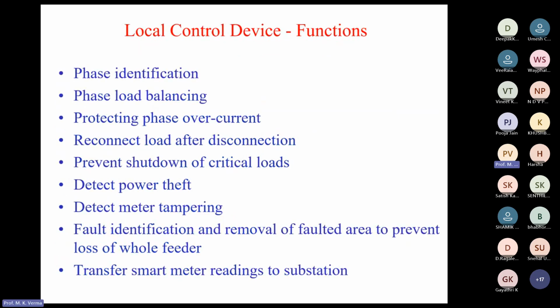The local control device's functions: it may identify the different phases and also the faulty phases, where the fault is, and it can deal with phase load balancing. It can protect the phases from overcurrent. It can disconnect loads if there is theft or something similar, and it can reconnect the load. If there is overcurrent, it can disconnect that consumer to protect the system, and again reconnect once things become normal.